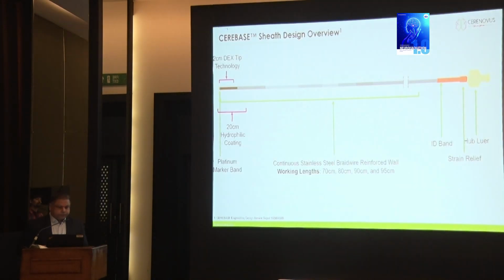About the design elements: very uniquely, what Cerebase did was they had a 2 centimeter Dex tip, and then 20 centimeter of hydrophilic coating. There's a marker here, which is 1 millimeter away from the tip, to visualize the sheath placement, then the strain relief, and the hub. It's a luer hub where, if you're using multiple catheters, you can use a W connector or a Y connector, or a single connector for stroke intervention.